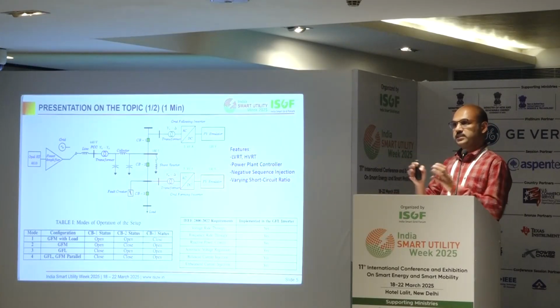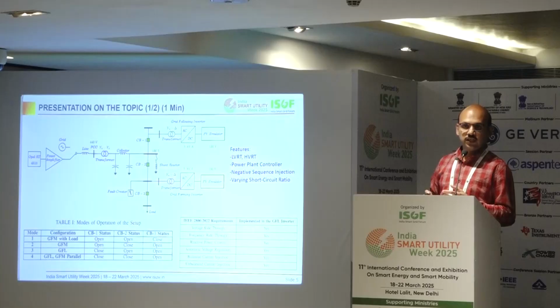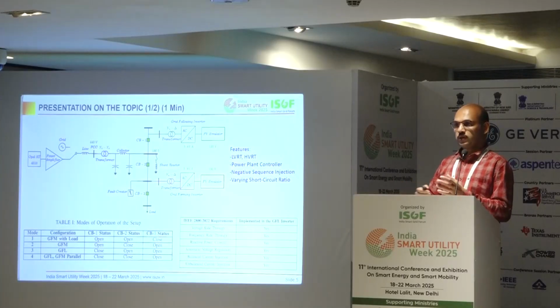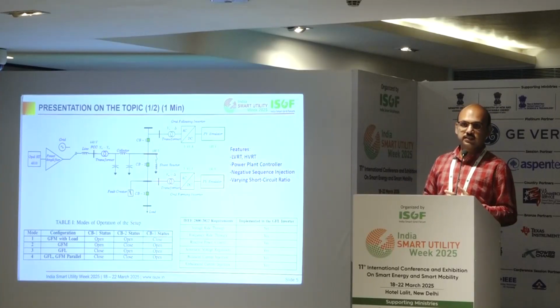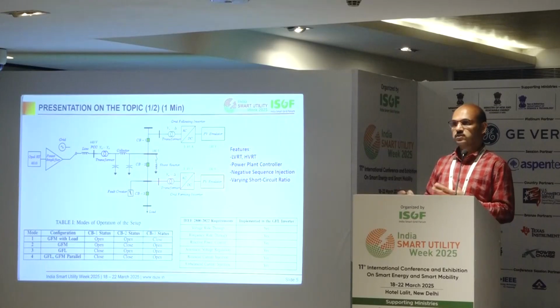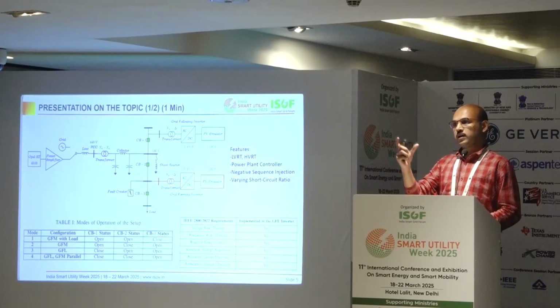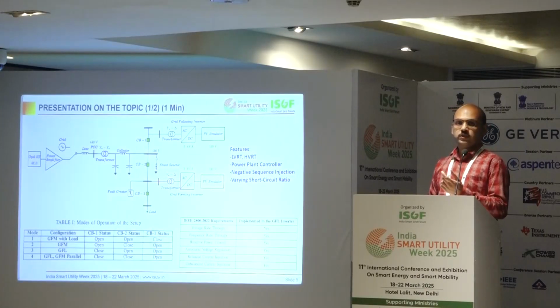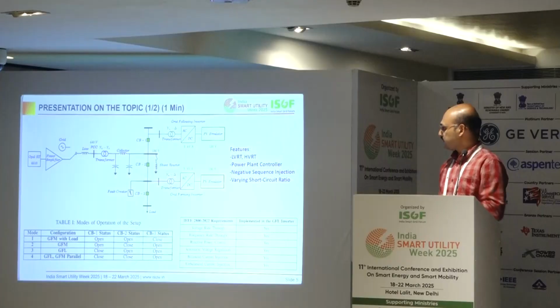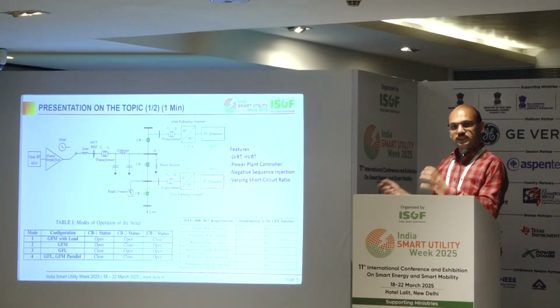It basically has resistances whose value you can change. So you can connect this resistance through a breaker across any phases you want to create a balanced or unbalanced fault. And then you can close the breaker. Again, it is a motorized breaker. So we have gone up to a 1 cycle fault. So you can have 1 cycle, 2 cycle, 3 cycle, whatever. You can create a physical fault.